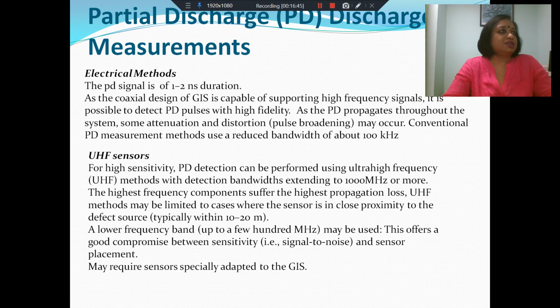The partial discharge will produce a signal of very small duration, in the nanosecond range. Now, the coaxial design of the GIS can support high-frequency signals. Therefore, even if you have small PD, it should be possible to detect the PD pulses with a high amount of fidelity. But you should remember that two issues are there. One is attenuation. As the signal travels along the path from the source to the sensor, there can be considerable attenuation. Also, there can be considerable dispersion. That is, different frequencies will travel at different speeds, and therefore the detected signal at the sensor will be considerably different from the signal at the source site.